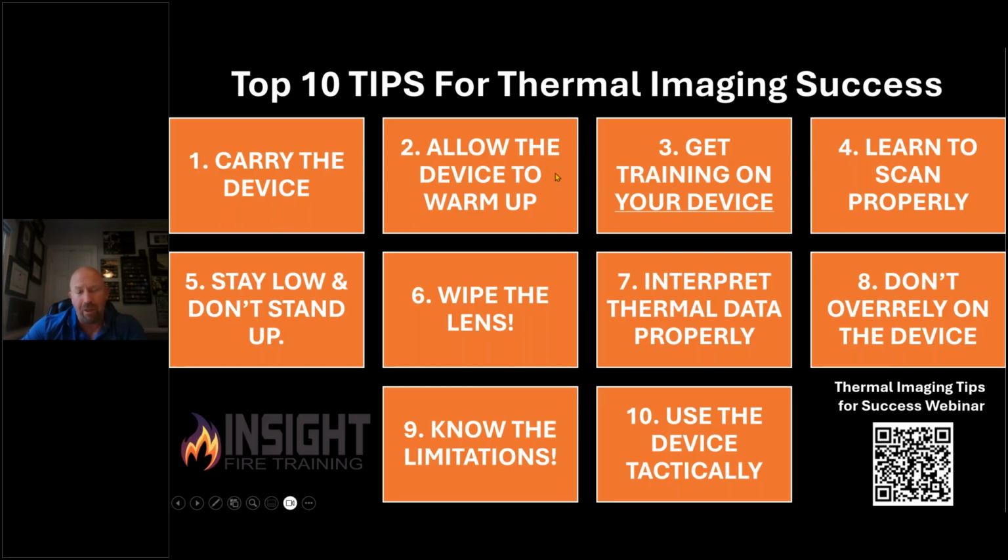Give it a second. The best way to do that is turn it on while you're on the truck and make sure that the batteries are good to go. And if you're using something like an Attack Pro VRS, you can easily switch it to survey mode before you come off the truck, so you're not doing buttons on the way to a 360 or when people are screaming and yelling. Biggest thing we see that firefighters don't do, and that's more of the organizational fault, is they don't provide training on the device.